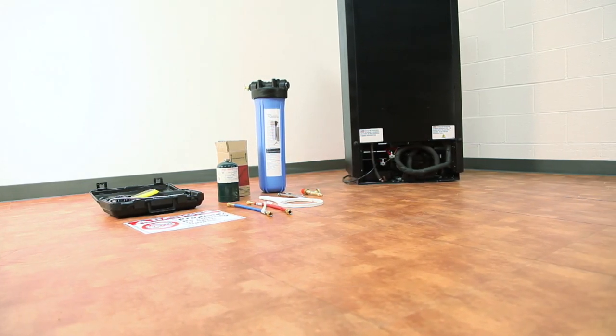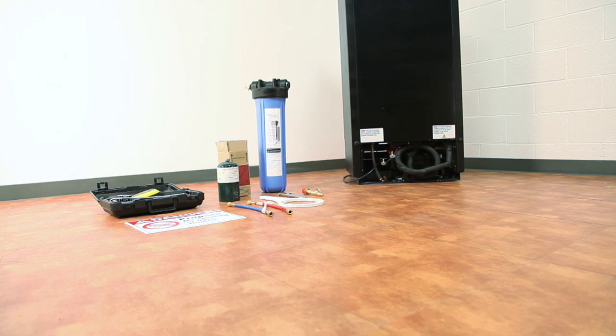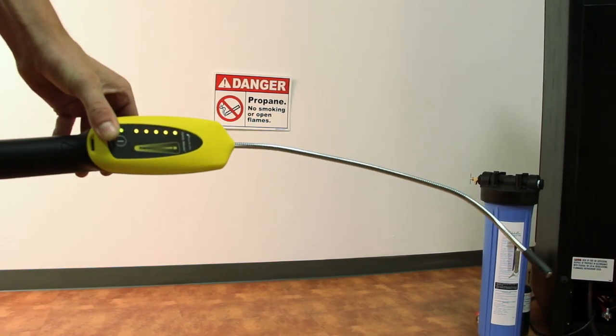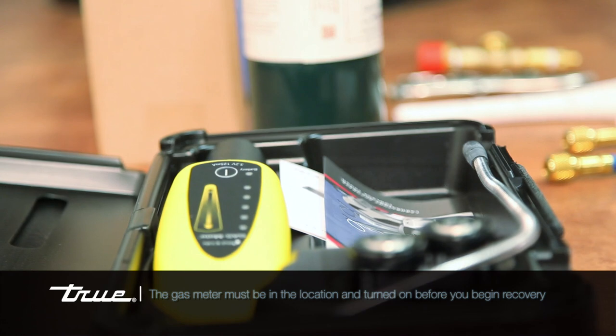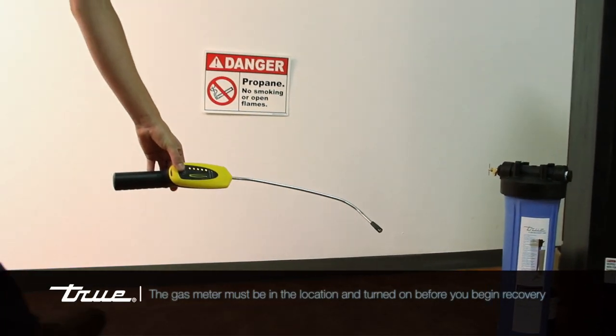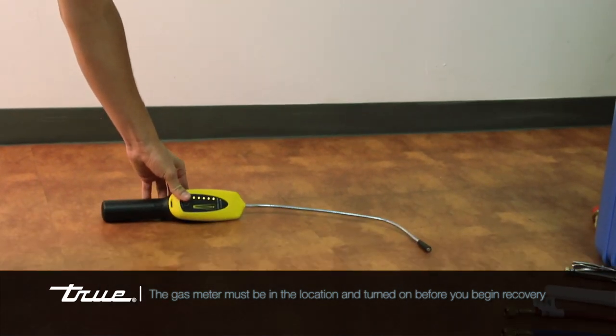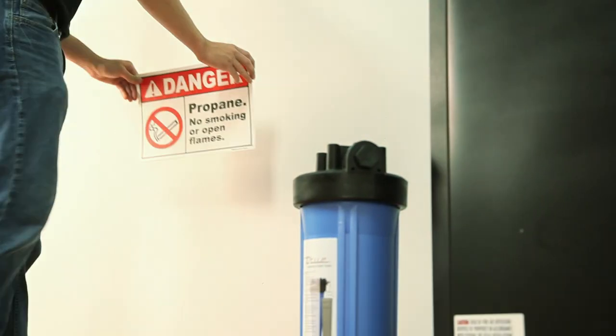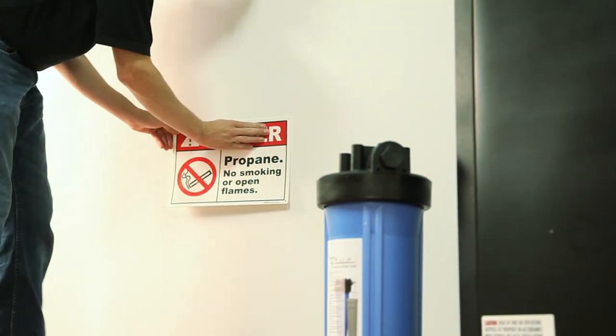The recovery process or any refrigeration-related repair should start by turning on your gas meter or leak detector. This tool is also part of the HC Toolkit and should remain on until the repair is completed. The safety placard needs to be in a location where the recovery or repair is taking place.